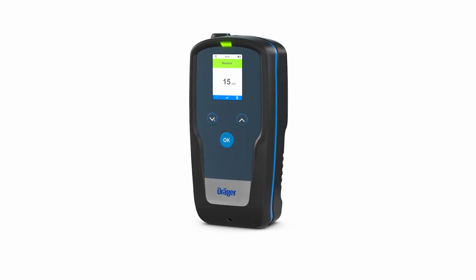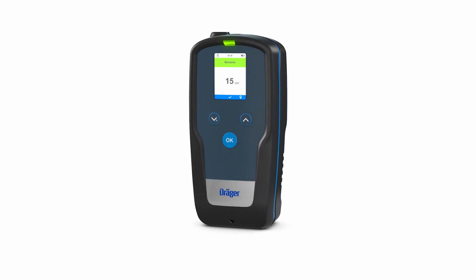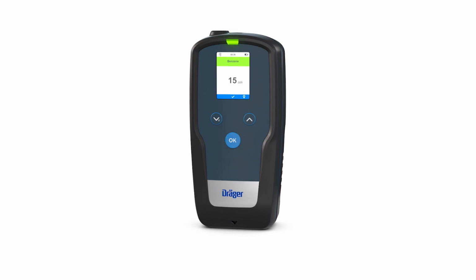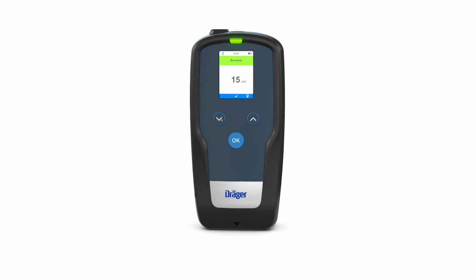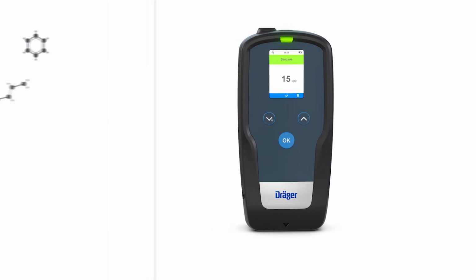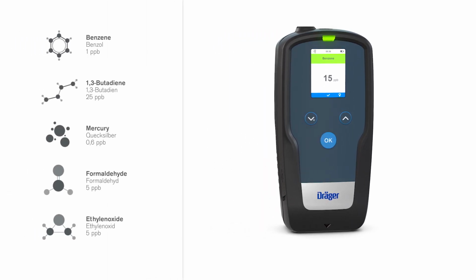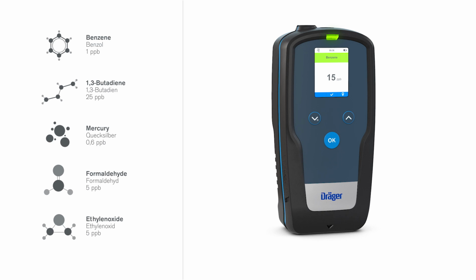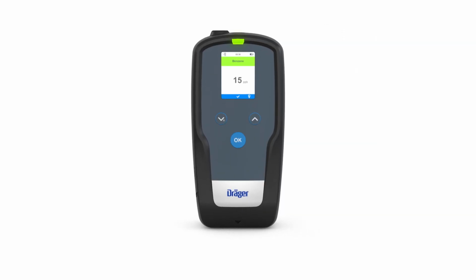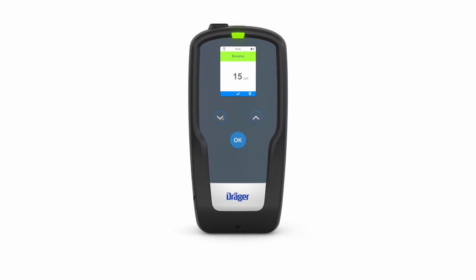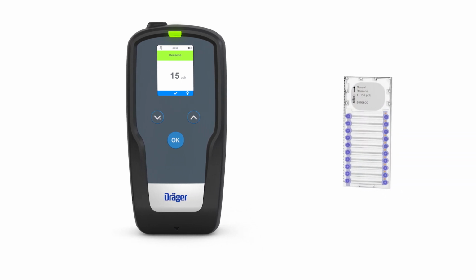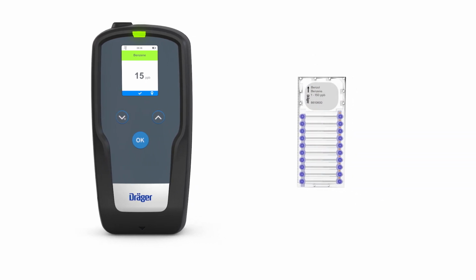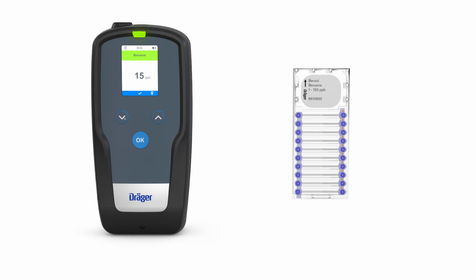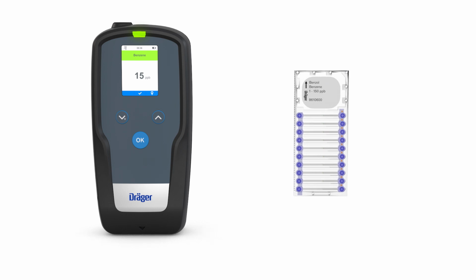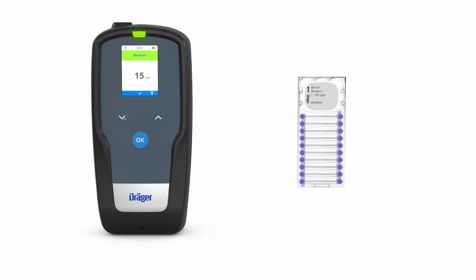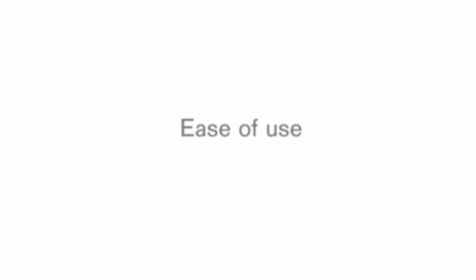The innovative Dräger X-act 7000 analysis system offers high-precision gas detection in the low ppb range. This is particularly beneficial for testing for benzene and other carcinogenic toxins. The system consists of the X-act 7000 analysis device and a range of microtubes for various gases and vapors. A single microtube can be used to perform 10 tests in a row. The system is continually being expanded to include testing for even more types of gases.